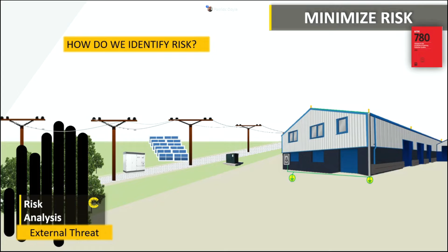So where did this really come from? If we look a little closely, we can see the lightning strike to the power line. We can see that the power line is feeding a transformer, which is feeding the building, which is also being fed by the microgrid. So it makes sense to me that it came from there, but can we really be sure? Maybe it was something else, maybe a faraway strike. A lightning strike from far away would follow the same path potentially, but maybe with a little bit less energy. It also could be a direct strike to the building with the lightning rods, which is going to have a lot more energy. So risk analysis is about minimizing the threats by examining every possible scenario. And each one, like a faraway strike to our PV array, will have its own unique consequence and, of course, its own solution.